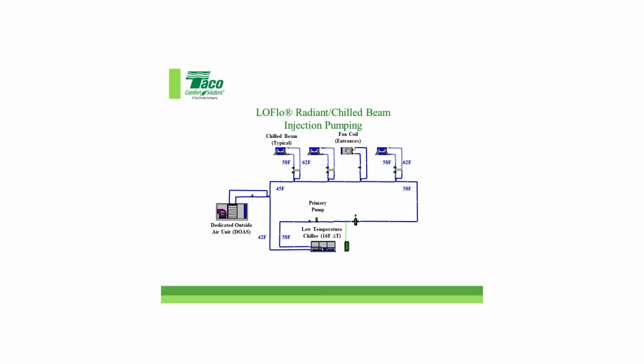Now I'm showing one of these for 1 chill beam, but at our factory we have one of these contraptions, our LOFlo block, for 9 chill beams. So you have one for a zone, not one for a beam. So you got to keep that in mind. And you can see we have one and it mixes here. So the water goes in, variable speed circulator, injection circulator, goes through the zone, thermostat controls this, humidity controls this, comes back in as the water warms up, we inject some cold water right here. So we're mixing right at the zone with our LOFlo block.